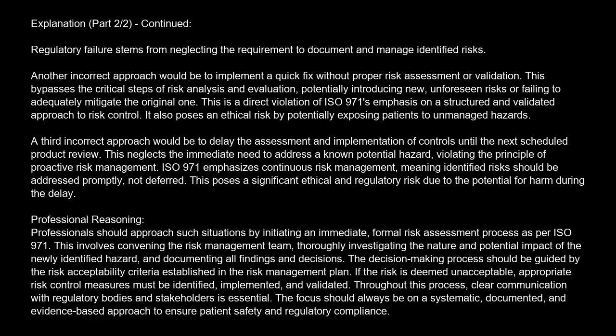Another incorrect approach would be to implement a quick fix without proper risk assessment or validation. This bypasses the critical steps of risk analysis and evaluation, potentially introducing new, unforeseen risks or failing to adequately mitigate the original one. This is a direct violation of ISO 14971's emphasis on a structured and validated approach to risk control. It also poses an ethical risk by potentially exposing patients to unmanaged hazards.